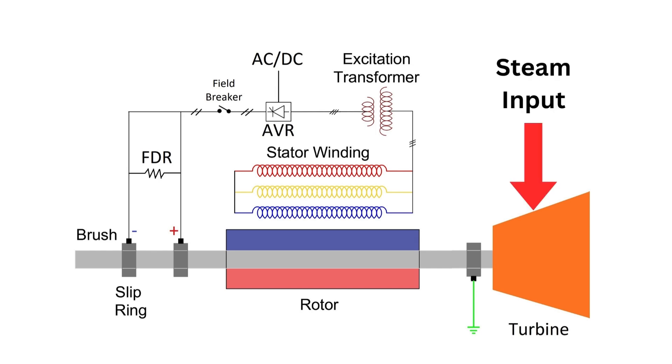Rotor speed is controlled by the steam input to the turbine and we adjust the rotor speed until the frequency matches the grid. This process also affects the induced voltage, which we can control using the excitation voltage to match the grid voltage.